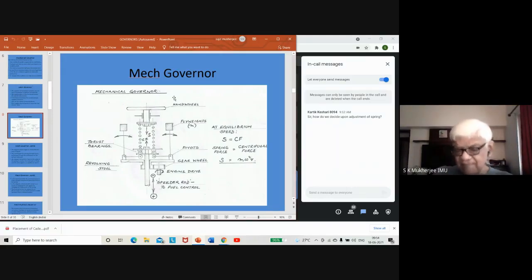This is made possible through a special arrangement which is a lever. So that lever is directly graduated with the RPM. So you want 50 RPM, you put it on 50 RPM. But what it is actually sending is an air pressure, a regulated air pressure going to that pneumatic piston, which will position the spring in such a way that the force will bring the fuel lever to a certain point where you will get 50 RPM. So these are all calibrated arrangements.